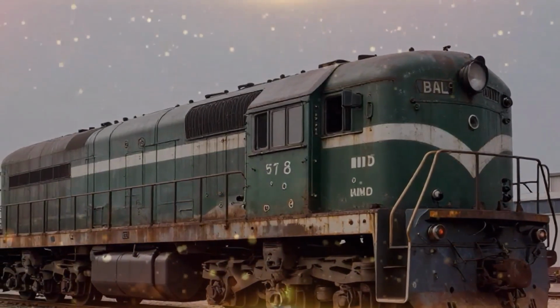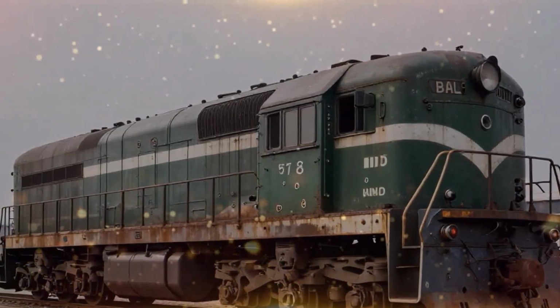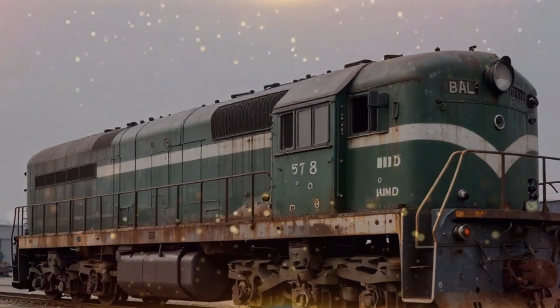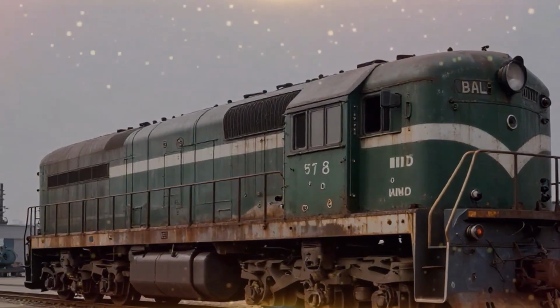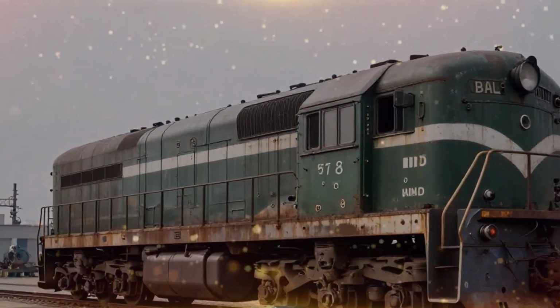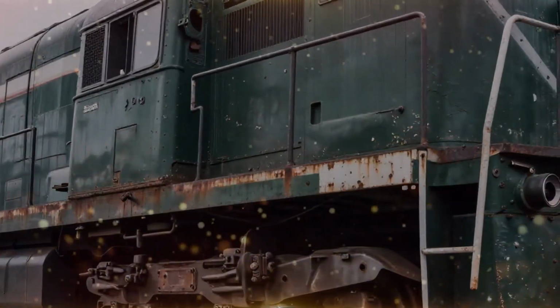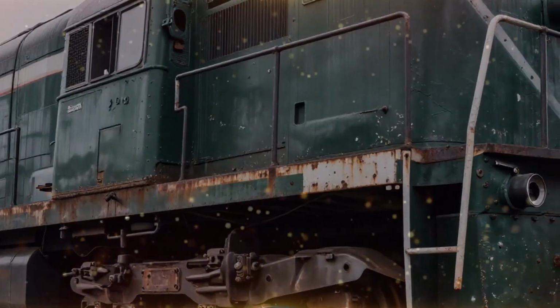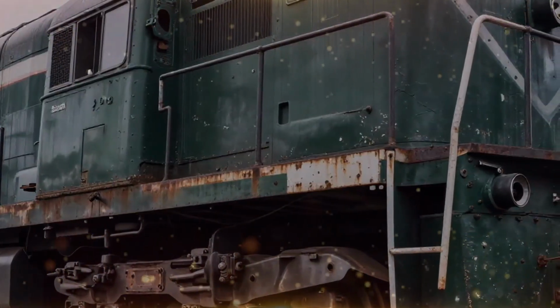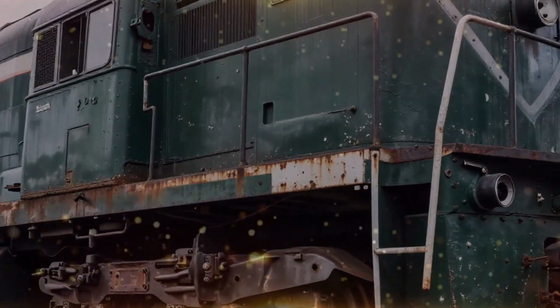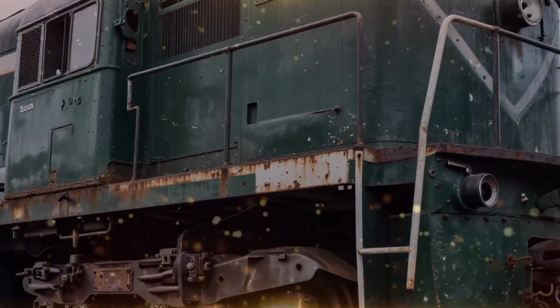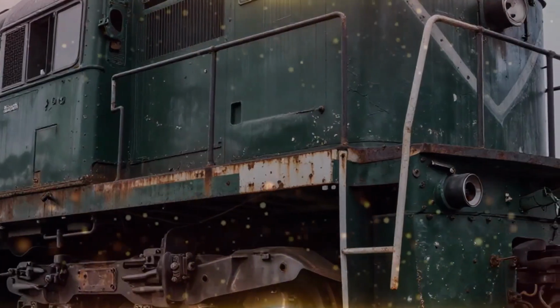The previous crews had chased this ghost for 6 months. They replaced the fuel pump because the engine died under load. They condemned the generator because the power cut out. They spent tens of thousands of dollars replacing heavy iron components because a 60-year-old piece of copper had a dirty face. They failed to understand that 1950s copper oxidizes differently than modern alloys.